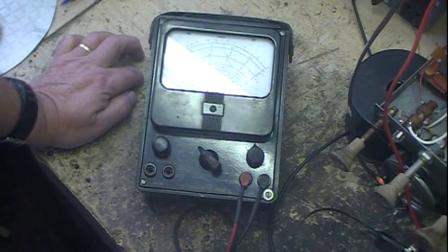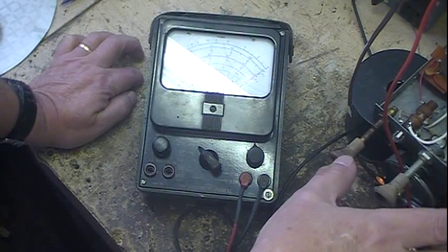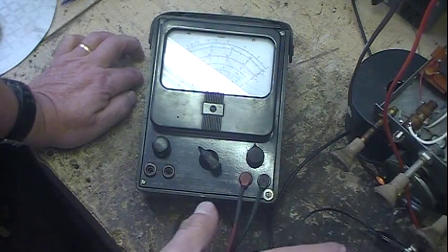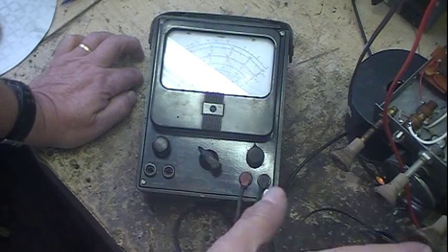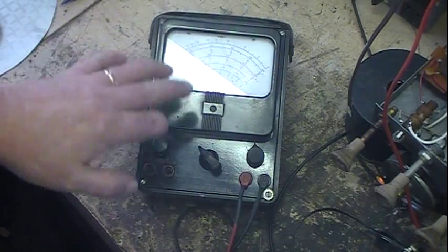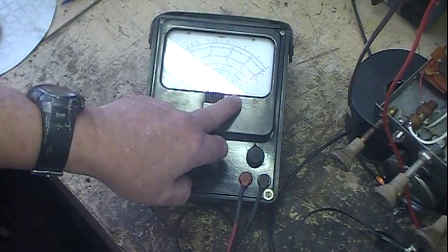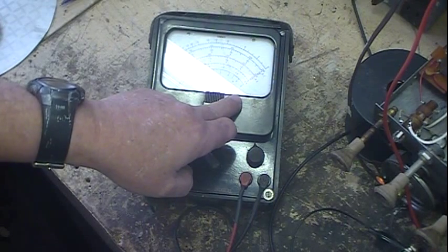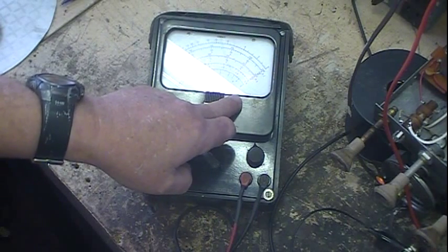And a 10 megohm or even 11 megohm or some high input impedance meter will pick up on that, and you'll actually think you got leakage. You really don't, you don't have any problems. This meter at 1,000 ohms per volt, it loads the circuit enough.